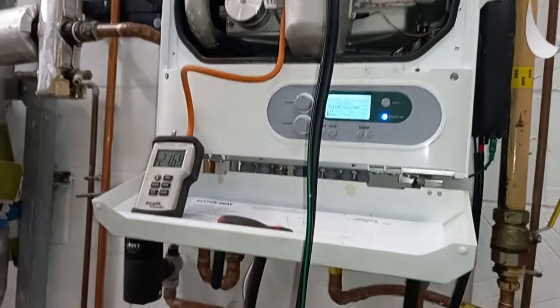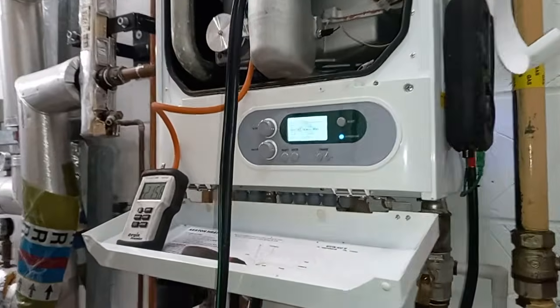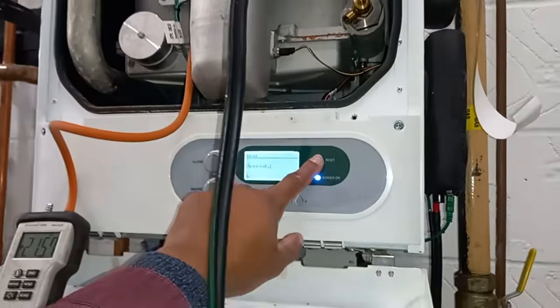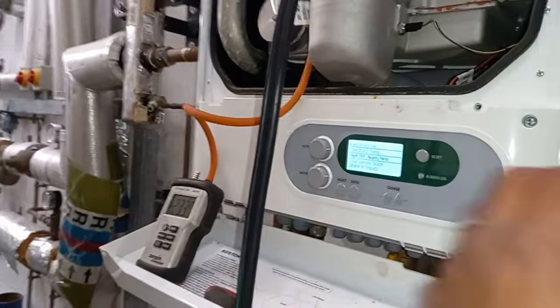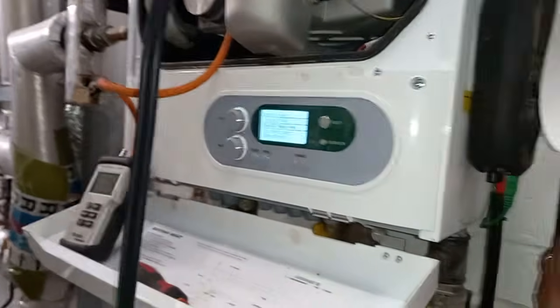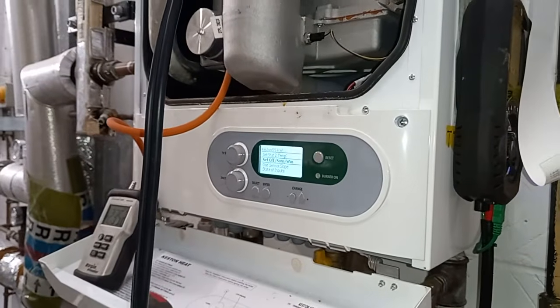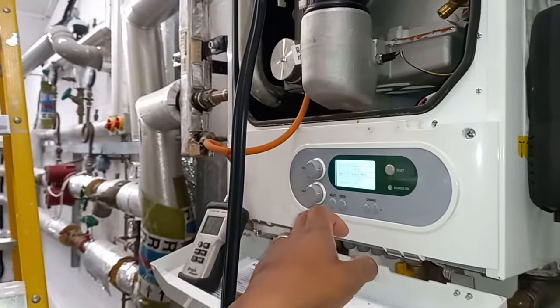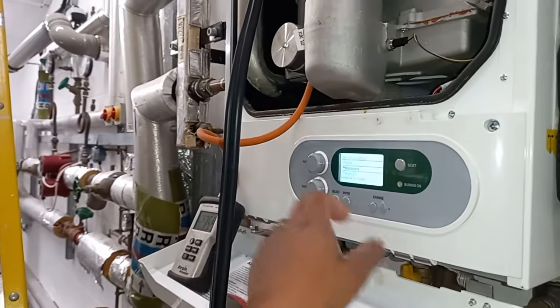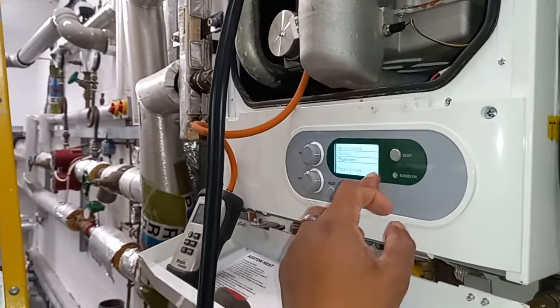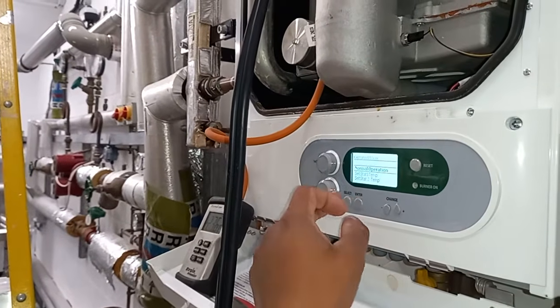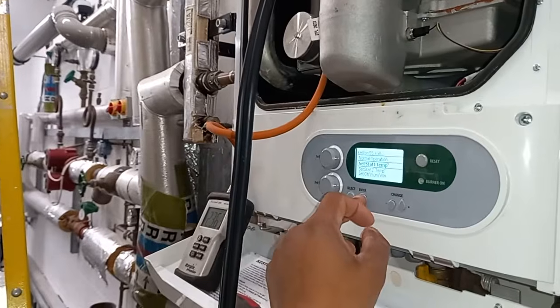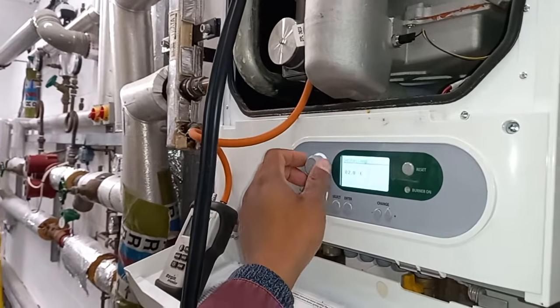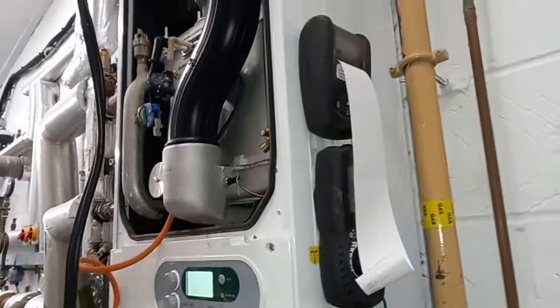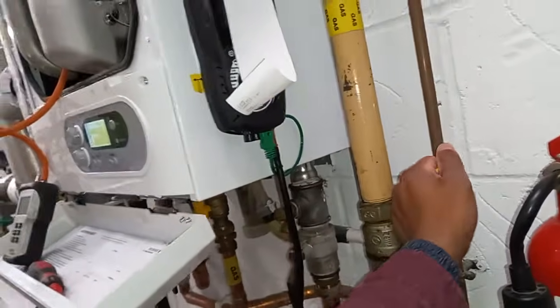So we've got our boiler on. We can reset our boiler. And I'm going to do a safety check. So we're going to wait for him to try and come back on or getting ready to light. So I've reset him, but he should be getting ready to light in a moment. I'm going to select a setting, maximum for example. Select. He's starting to get ready to start up. My fan's running.